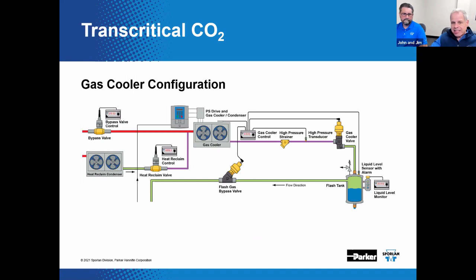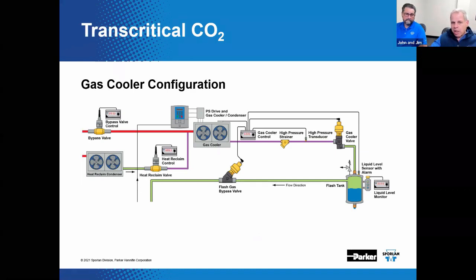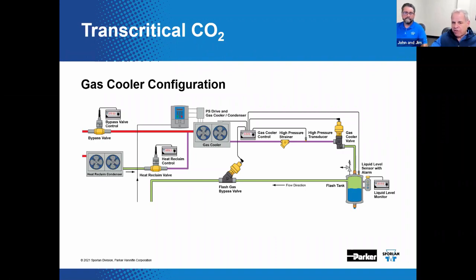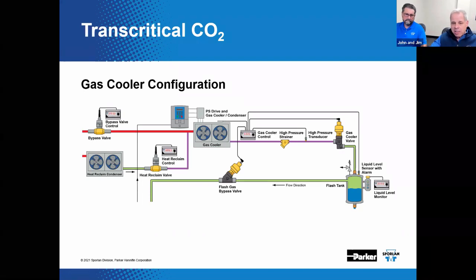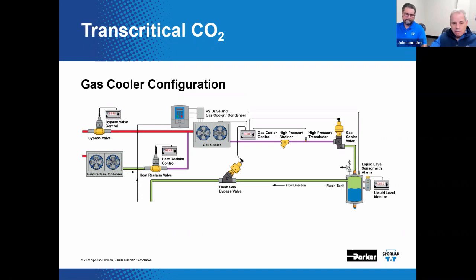The desuperheated gas leaves the gas cooler and expands as it flows through the gas cooler valve. Liquid and vapor are present and collect in the flash tank. There's a flash tank depicted. And the gas cooler valve regulates gas cooler pressure. The flash gas bypass valve allows vapor to leave the flash tank and travel to the suction of the medium temperature compression stage. This helps to regulate the flash tank pressure. Downstream of the flash tank, CO2 pressures are subcritical and operate in a similar fashion to any other HFC system. The gas cooler valve controls the gas cooler pressure. The flash tank is designed to separate liquid and vapor CO2. The vapor is then bled to the suction of the medium temp compression stage to maintain that saturated pressure in the flash tank, and so on.